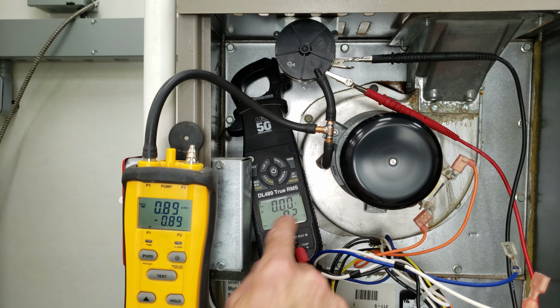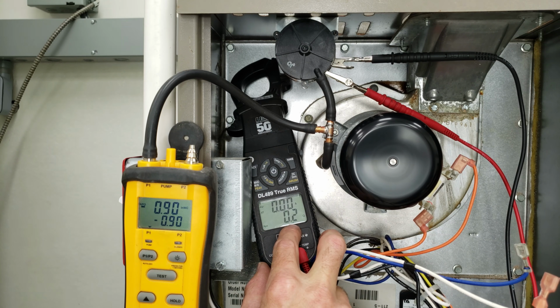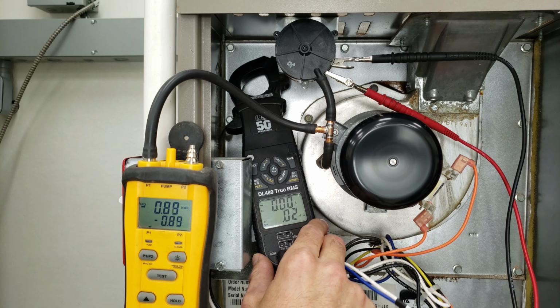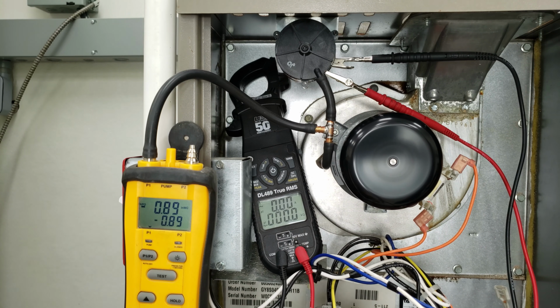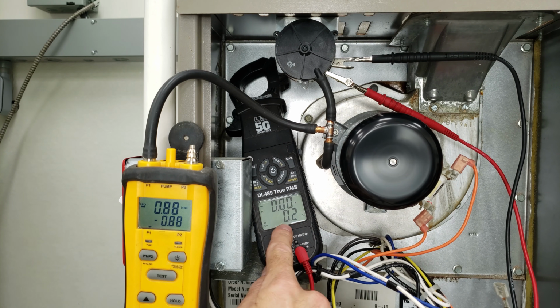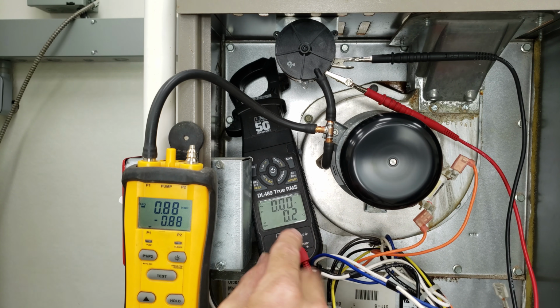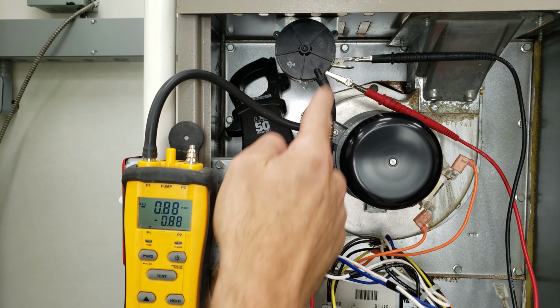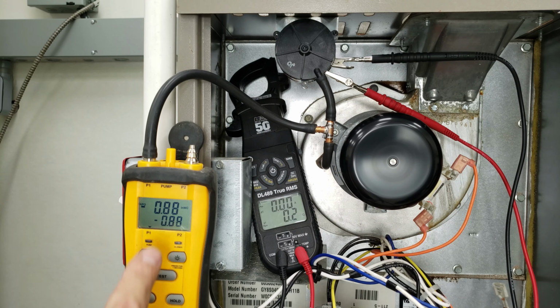So you see we're measuring 0.2. Now that's not the continuity function. So that is just the electrical resistance function instead of continuity, so it won't be making that beeping noise. But we're measuring 0.2 ohms of electrical resistance across that switch, and that may just be due to the probes themselves, the alligator clips, but that switch is now closed.